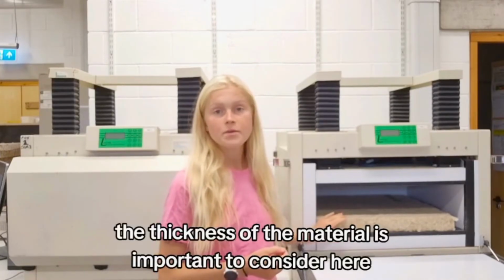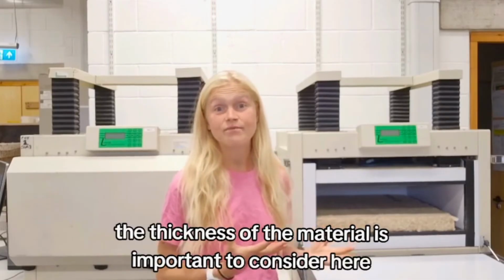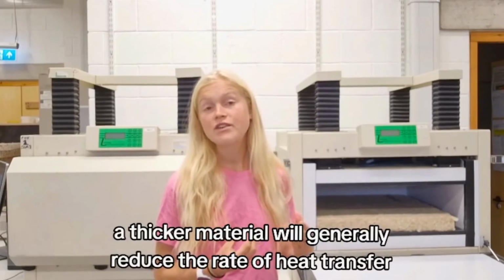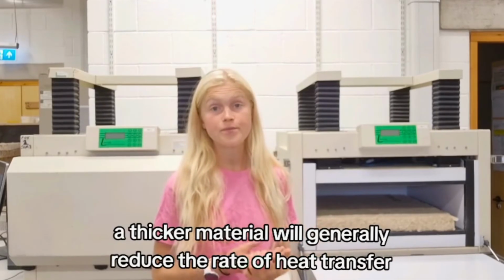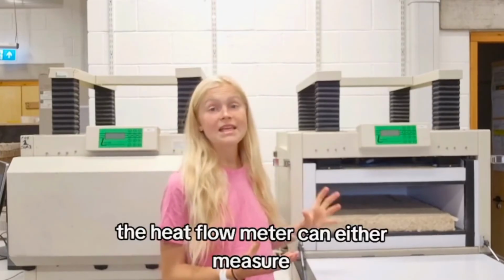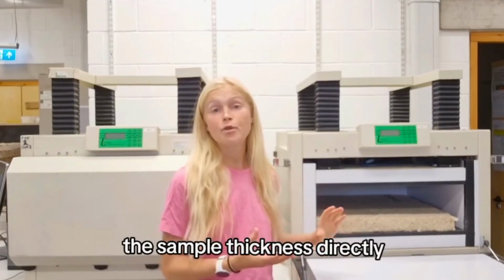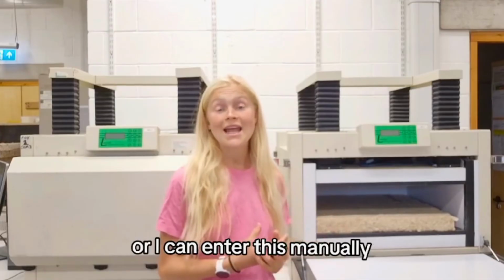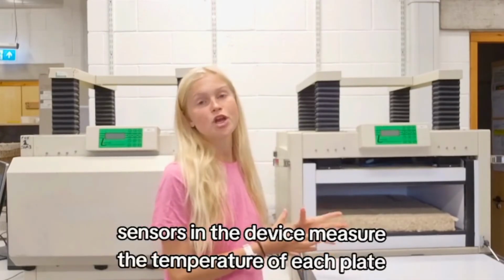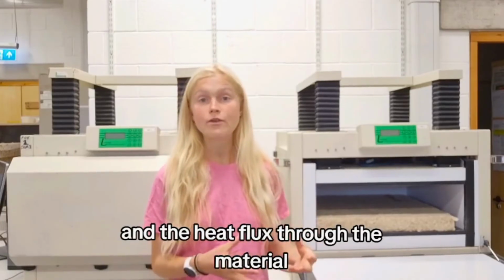The thickness of the material is important to consider here. A thicker material will generally reduce the rate of heat transfer. Before I make a measurement, the heat flow meter can either measure the sample thickness directly or I can enter this manually. Sensors in the device measure the temperature of each plate and the heat flux through the material.